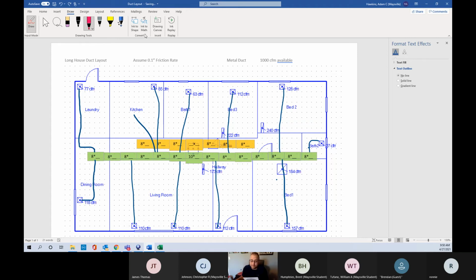Here's what he did. He goes to each of these rooms, and it blows my mind that he even knew to do this. He puts a 10 or 12-inch supply and a 10 or 12-inch return in each of these recording studio rooms, in each of these booths. And then he coils the duct 100 feet like a snake in the attic, and then runs it all to his main system where he's got dampers controlling each one of them. Each booth is run off a thermostat. Why did he do that?